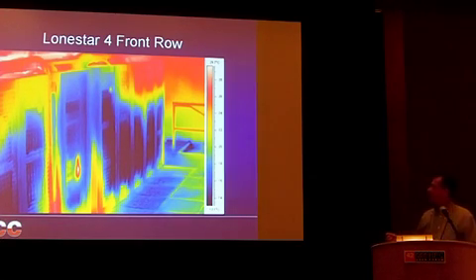What I'm showing here is the front row of Lone Star 4 with the thermal imaging, with the scale here so you can see the cooling. A couple of things to point out: you notice there's some bleed over of the air, hot air into the tops of the racks, but this is only about 80-degree temperature air. Again, this was when the system was running in full production.